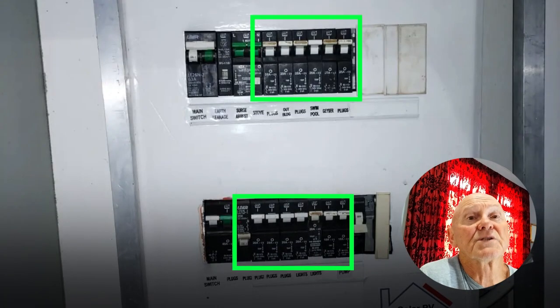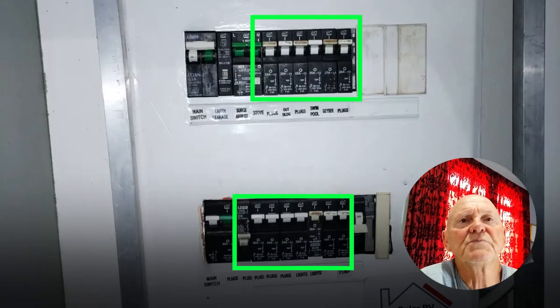Something interesting, a circuit breaker with a white toggle or a switch is designed to trip when it senses a 10% overcurrent. In other words, when a 20 amp circuit breaker senses that it reached 22 amps, power is off. There is no fault on the system. You only used more than what the device was designed for. Or in plain English, if the protector is too strong, it might not cut off in time, or it will cause damage to the wiring. A DB upgrade should include checking that the protective switches are matched properly.